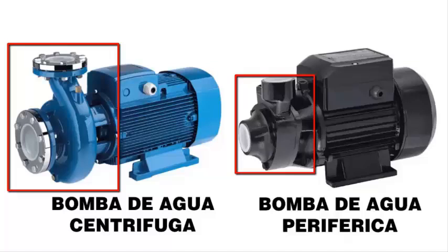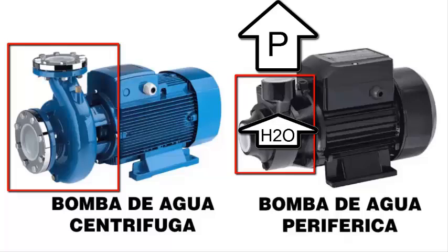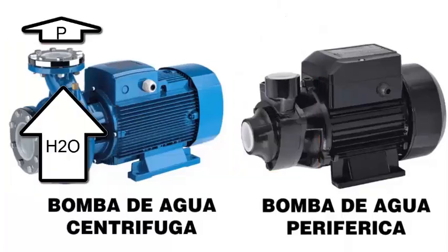3. Impeller Size and Efficiency. The impeller of a peripheral pump is smaller, but its design allows it to achieve high pressures without needing large diameters. This makes it ideal for low-flow, high-pressure applications. Centrifugal pumps need larger impellers or higher speeds to generate equivalent pressures, which is inefficient for low-flow applications.